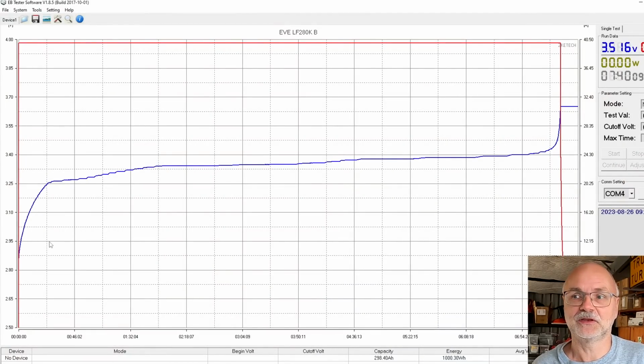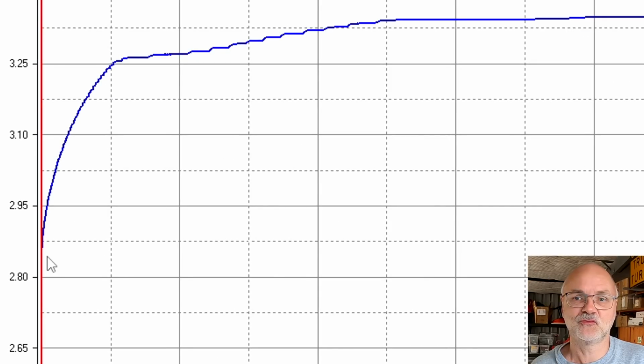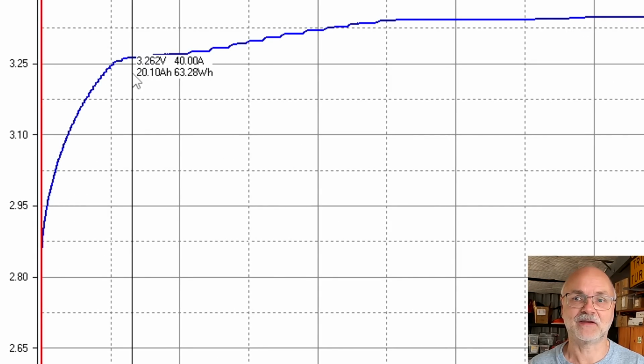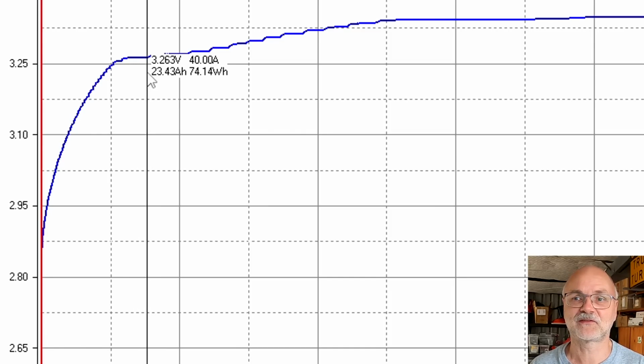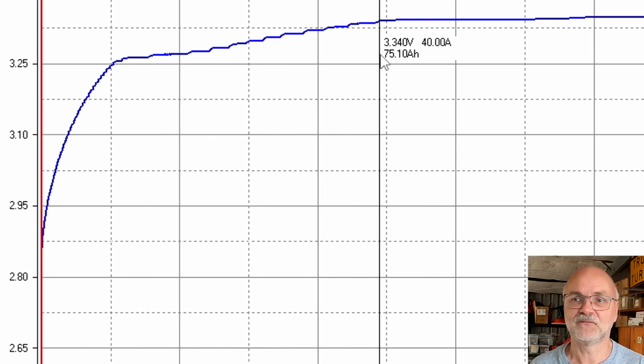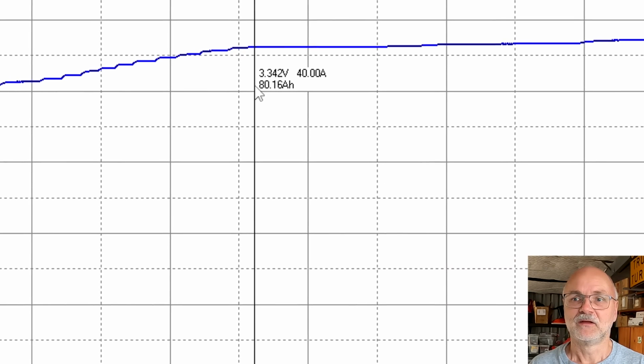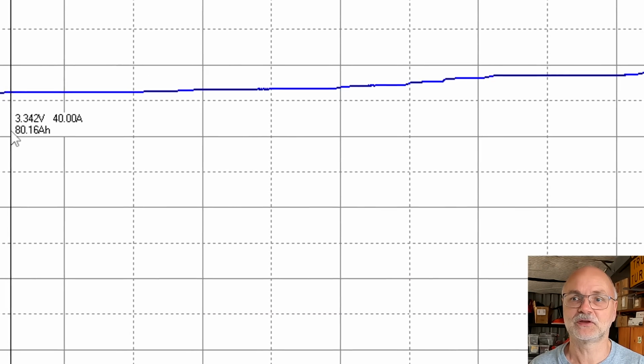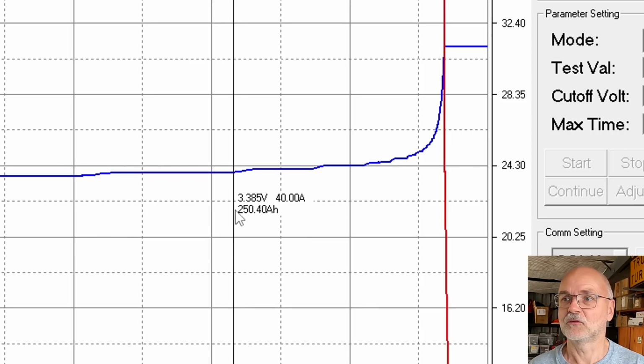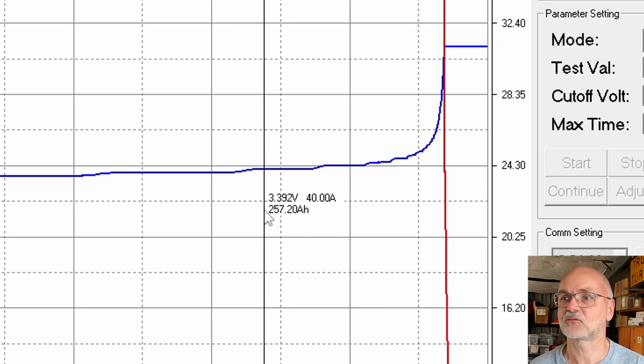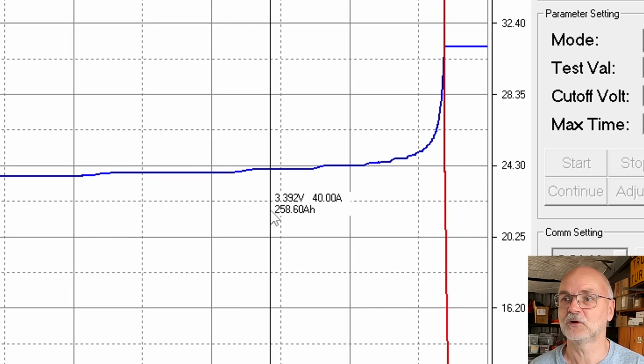And here we are. We have the typical charge curve of a lithium iron phosphate battery, starting from around 2.8 volts. Then we start entering the flat part of the curve at 20 ampere hours charging capacity, already 3.26 volts. A little bit of increase in voltage here, then 3.34 charging voltage at 80 ampere hours, all the way to 3.39 volts at 260 ampere hours already.